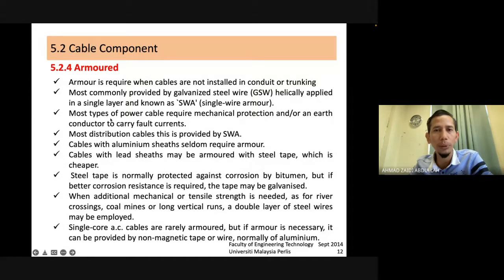So most types of cable power require mechanical protection. Most distribution cable is provided with SWA, okay. And then cable with aluminium sheath seldom requires armour. So normally yang copper lah, copper we cover with the armour. And then cable with lead sheath may be armoured with steel tape, which is cheaper. This one. And then steel tape is normally protected against corrosion by bitumen. But if better corrosion resistance is required, the tape may be galvanized. So this is some type of the, what we call it, armoured punya sample lah.